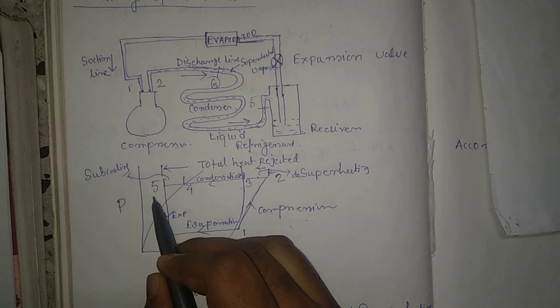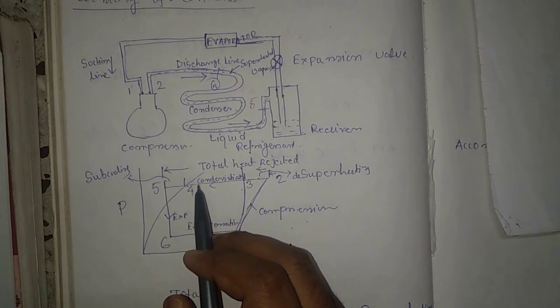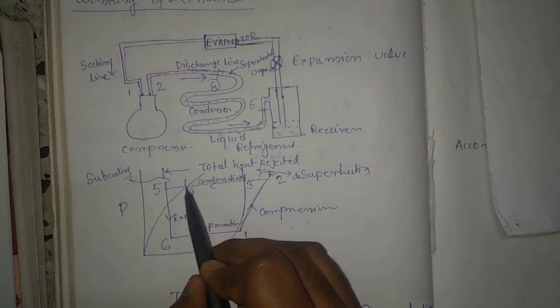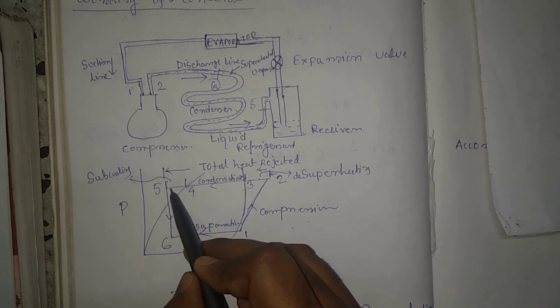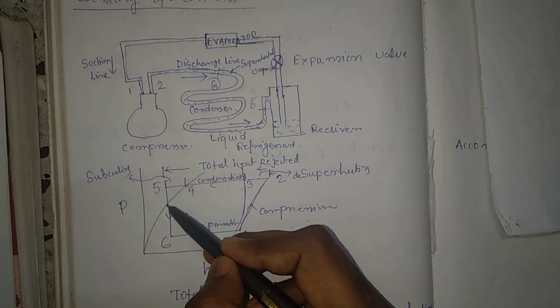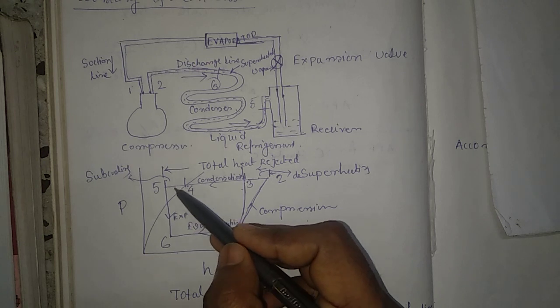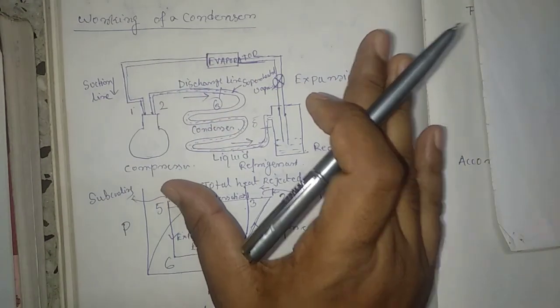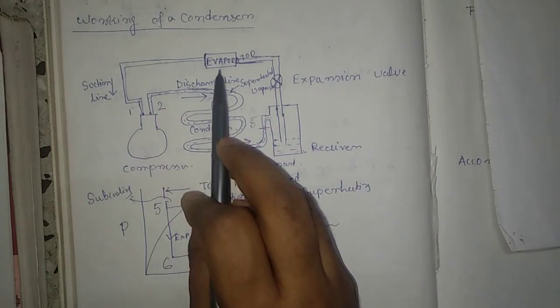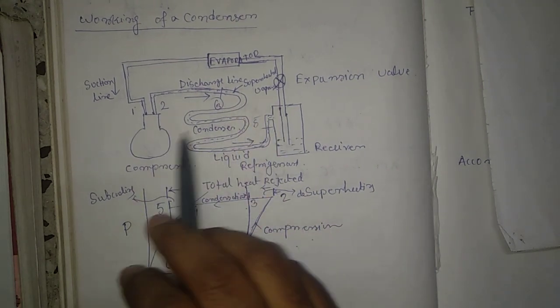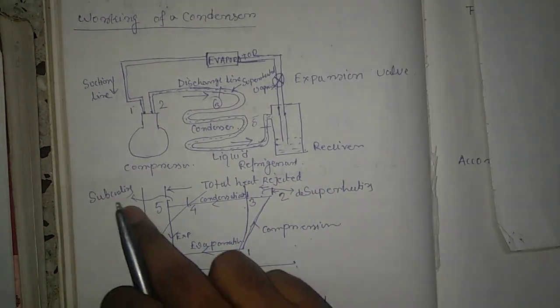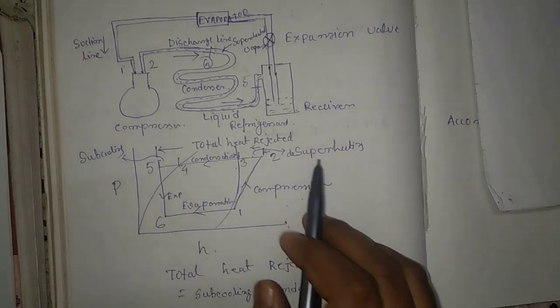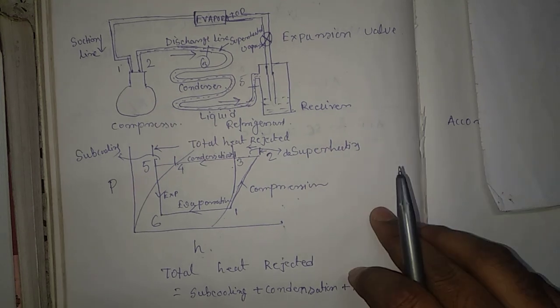In the last part, process four to five, the temperature of the liquid refrigerant is reduced below its saturation temperature — this is called sub-cooling. This is done in order to increase the refrigerating effect. This completes the basic VCR cycle shown in the diagram, with compressor, evaporator, expansion valve, and condenser. In summary, the condenser works through three processes: de-superheating, condensation, and sub-cooling.